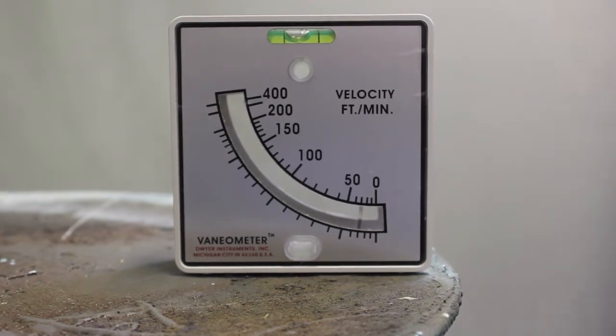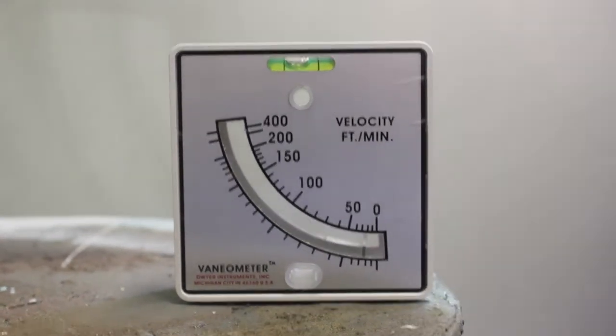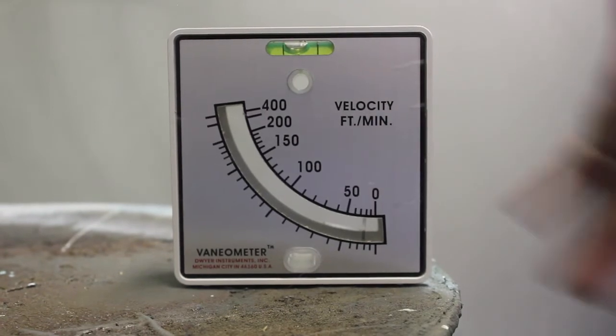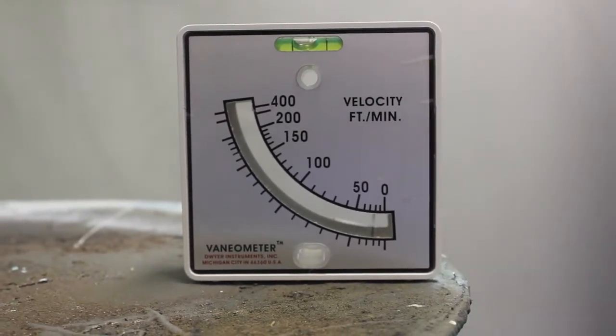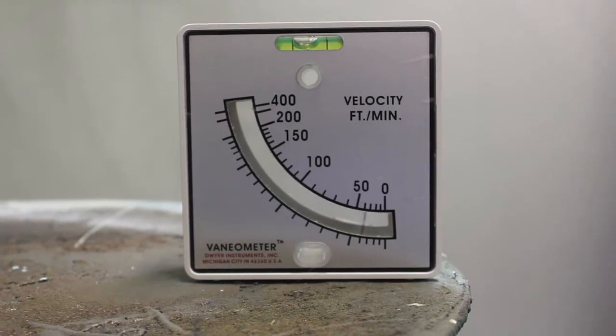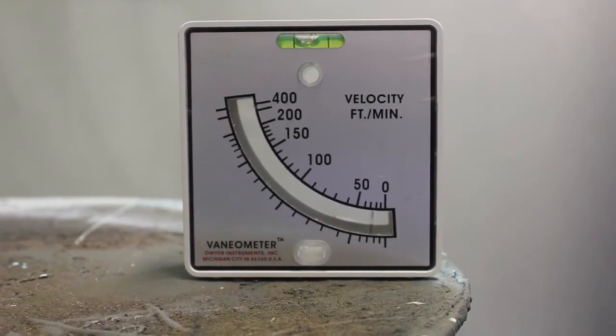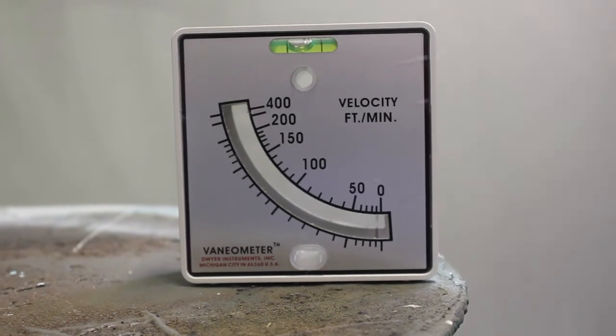The way the tool works, we want to make sure it's on a level surface and that this opening is allowing the air to pass through and hit the little vane, as it is called, inside this device. That vane movement shows us how much airflow we have in our booth.